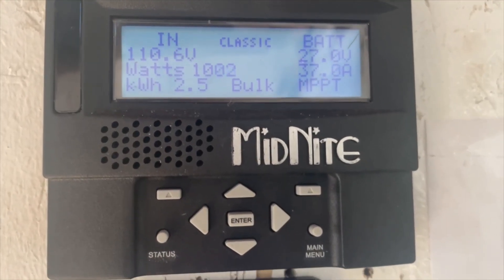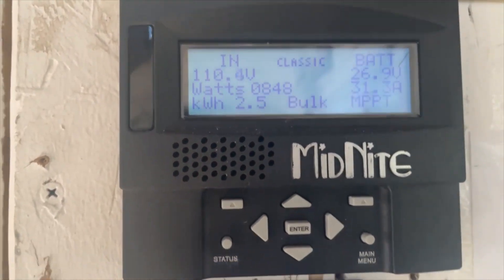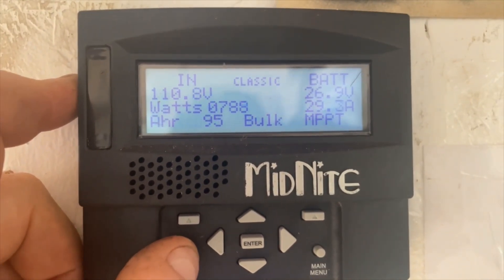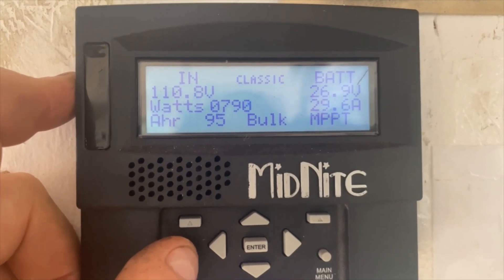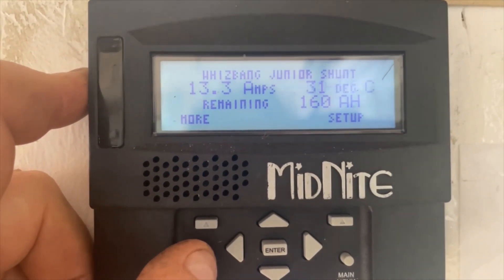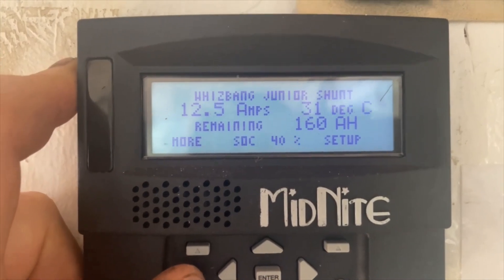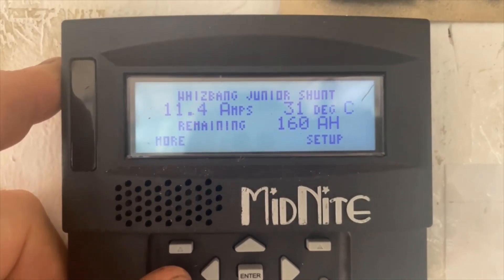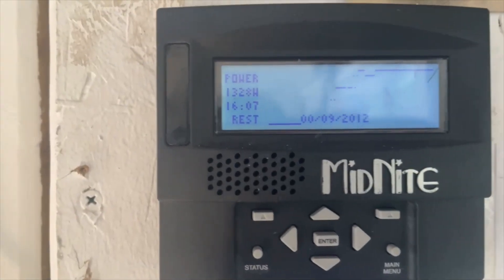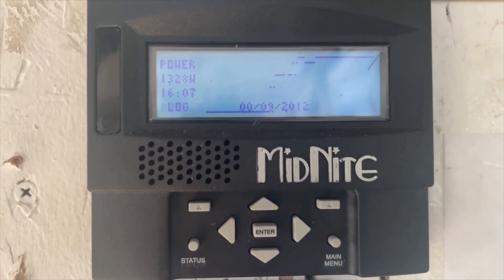This is the remote panel from the MidNite Solar. Right now it's about 1 o'clock in the afternoon on November 1st, so we're getting 800 watts of power out of the panels at 115 volts. About 13 amps is going into the batteries — the rest is keeping the cabin going. State of charge is 40%. This Victron thing works off the shunt that's inside the MidNite Solar breaker panel.